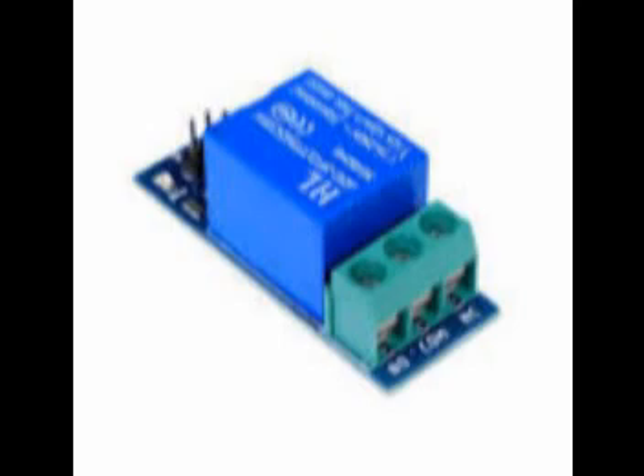They then send a signal to trip the main circuit breakers, opening the circuit and isolating the faulty section of the line. So they prevent a local problem from cascading and taking down a whole area. Exactly. They contain the fault, protect expensive equipment, and maintain stability on the rest of the grid. They really are guardians of our power supply.